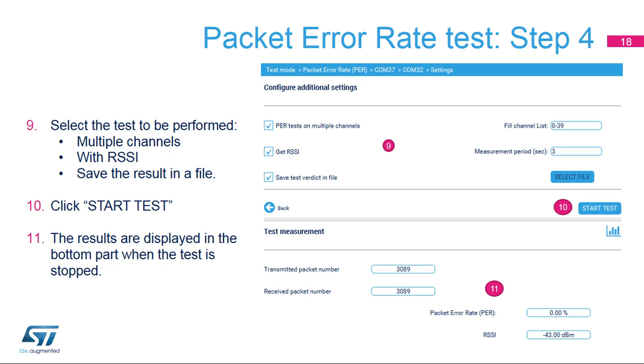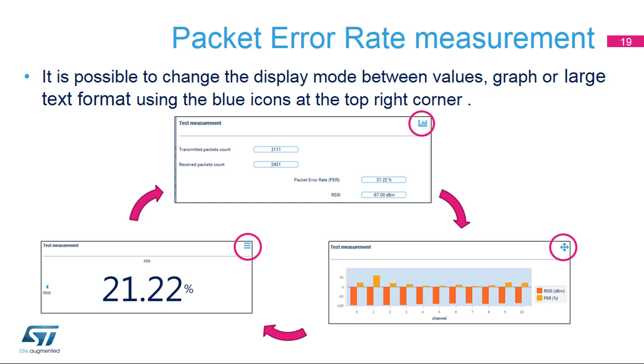The test starts and begins measuring. When PER TESTS ON MULTIPLE CHANNELS is selected, the test stops when all channels have been scanned. Click STOP TEST to get the results. It is possible to display the results in a graph or in a large text format — use the blue icon at the top right corner of the result area to switch the display mode. The graph view gives an overview of the measurements in real time, while the large text format can be visible far from the computer when testing over long distances.